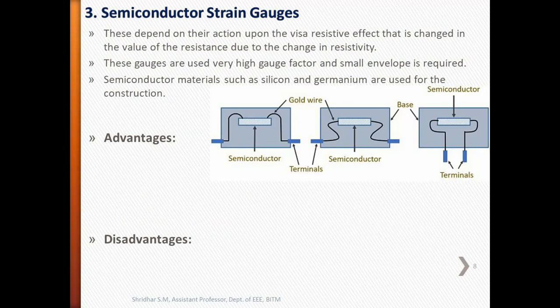Next we will discuss semiconductor strain gauges. Semiconductor strain gauges depend for their action upon the piezoresistive effect, that is the change in value of resistance due to change in resistivity. These gauges are used where a very high gauge factor and small envelope is required. Semiconductor materials such as silicon and germanium are used. The figure shows examples of semiconductor strain gauges where a semiconductor material is placed on a base and terminals are taken out using a gold wire.